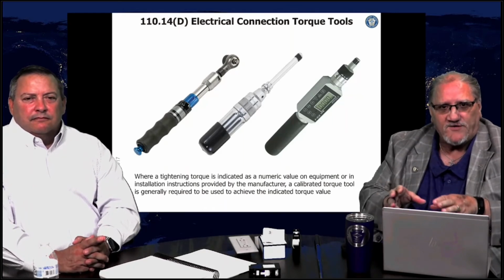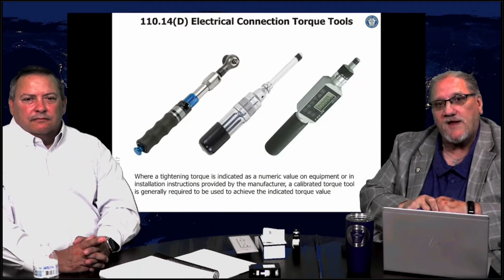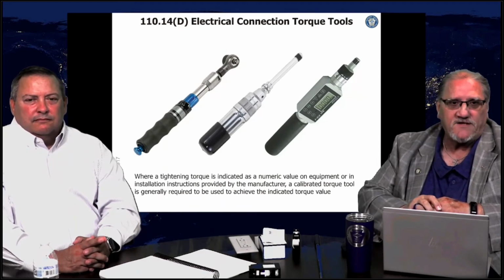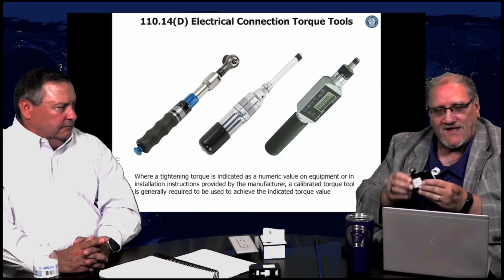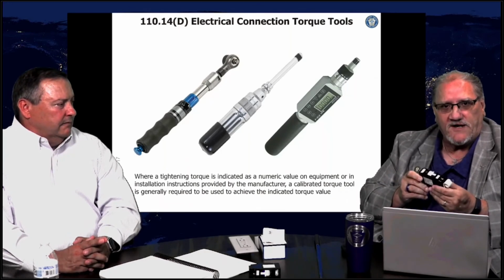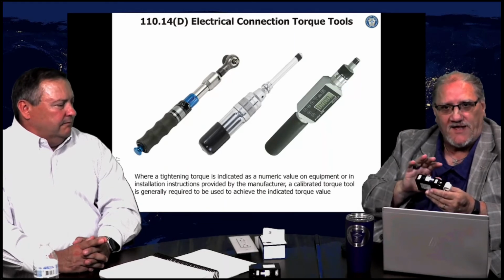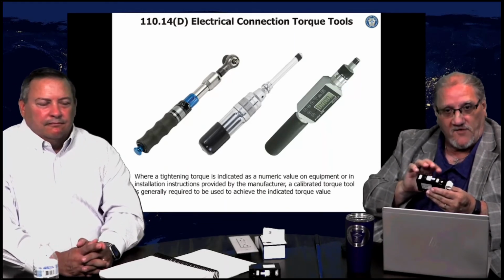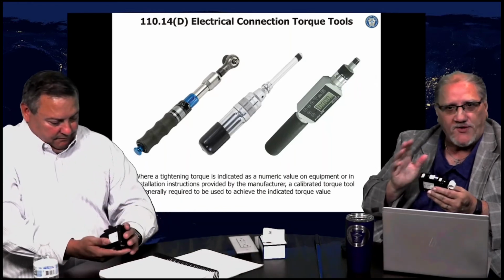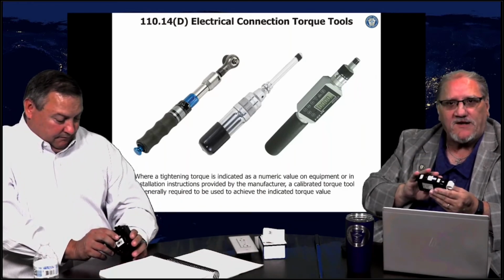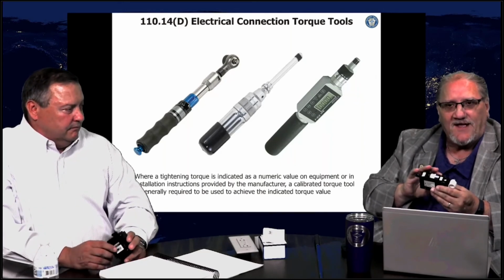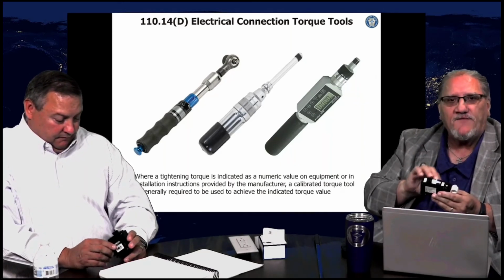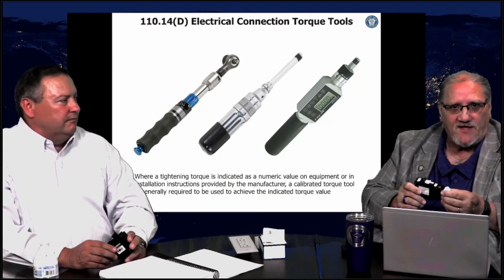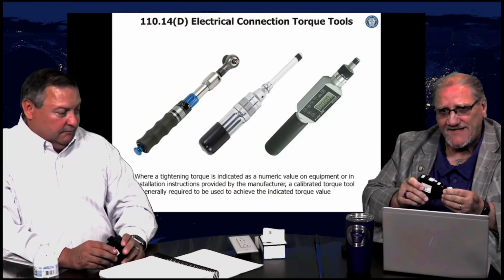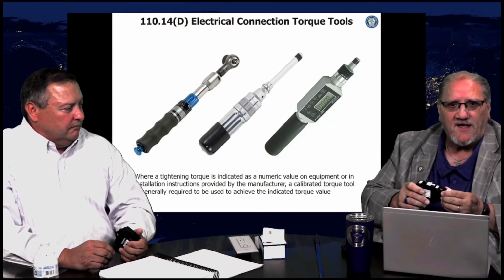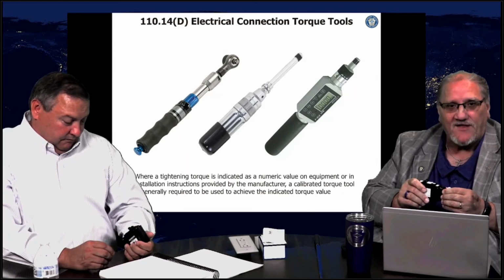And when we say manufacturer's specifications, we're not talking manufacturer's recommendations. We're talking specifications. In other words, when Siemens got this overcurrent device listed by a third-party testing agency, UL or Intertek or whoever, that torquing value that has to be achieved was part of the listing of this particular piece of equipment. So it's more than a manufacturer's recommendation. It's manufacturer's specifications to meet their listing requirements.